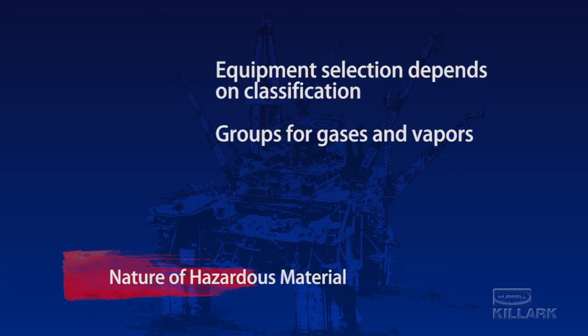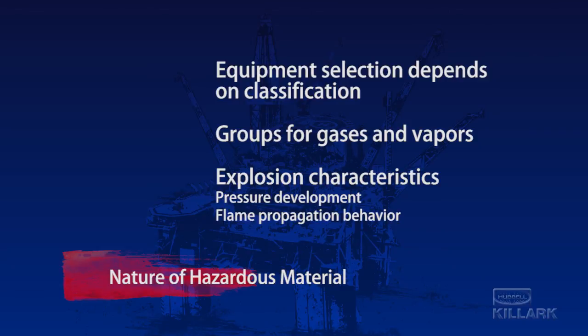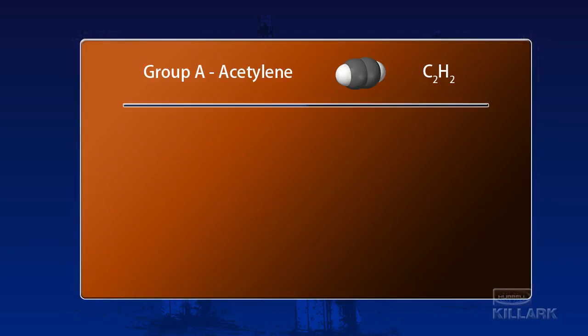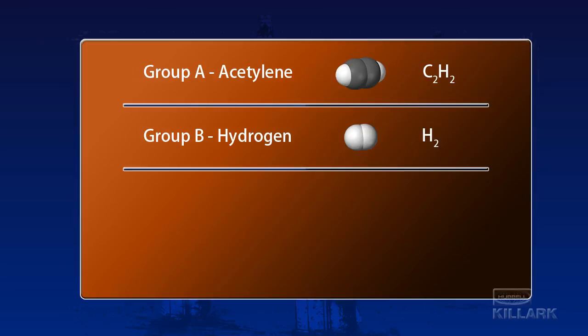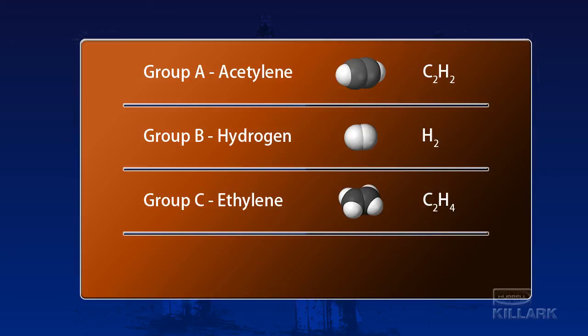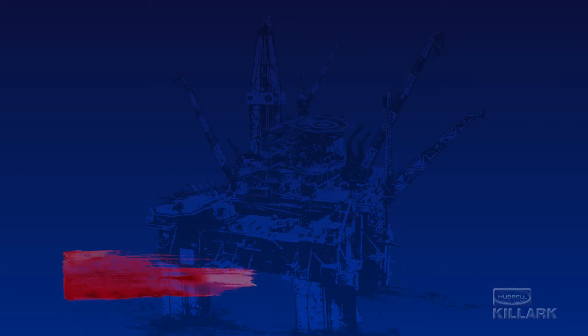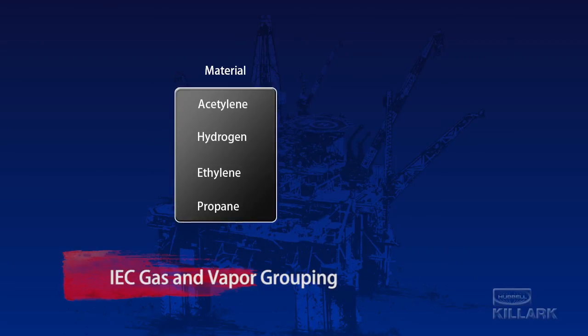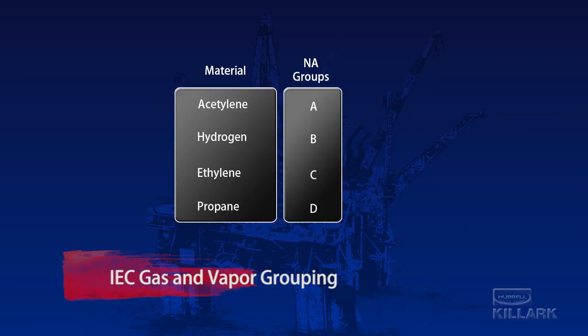Gases, vapors, and flammable liquids are assigned to groups based on the similarity of their explosion characteristics to the typical material used to represent the group. Within the North American class and division system, Group A is represented by acetylene, Group B by hydrogen, Group C ethylene, and finally Group D includes materials comparable to propane. The zone system has a similar method for dividing these hazardous materials into groups using the same explosive properties, but the letter designations are the reverse of those used with divisions.